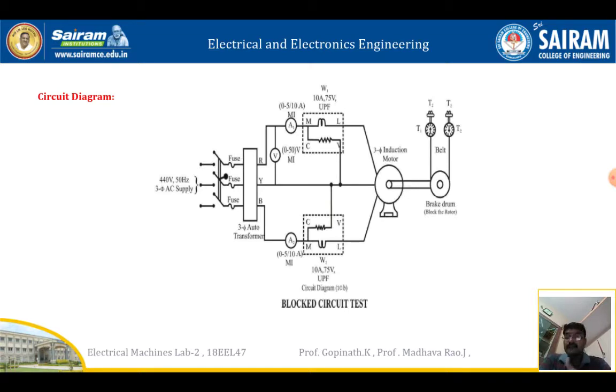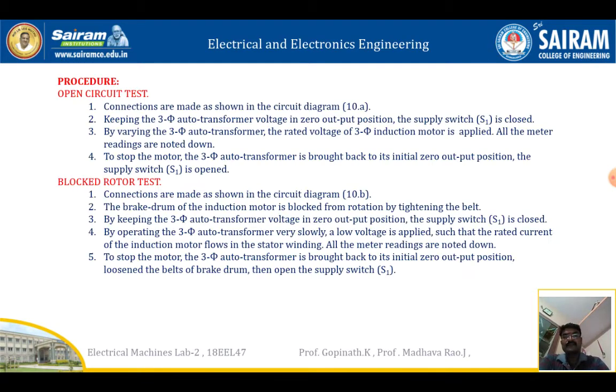We should take more caution in the blocked rotor test, because the motor is not going to run and at the same time the current value will increase. So we should go up to the rated current, then stop, and take the corresponding voltmeter and wattmeter readings. This is the procedure for the open circuit test and blocked rotor test.